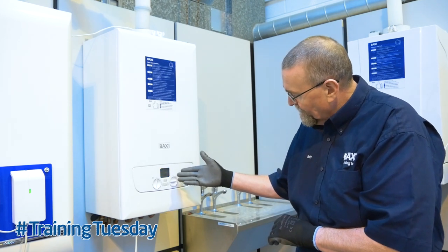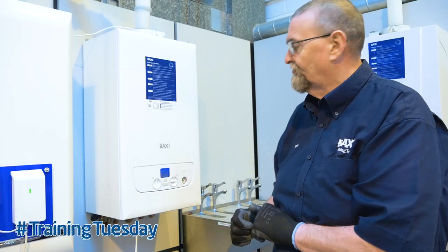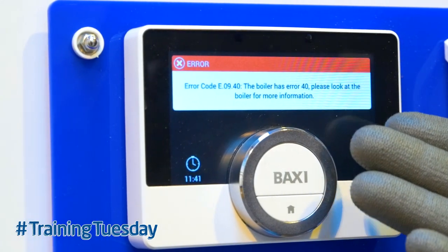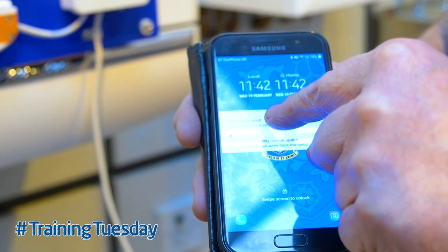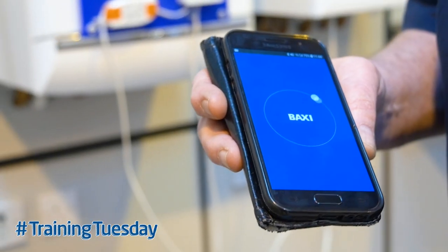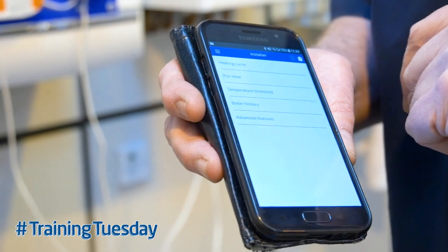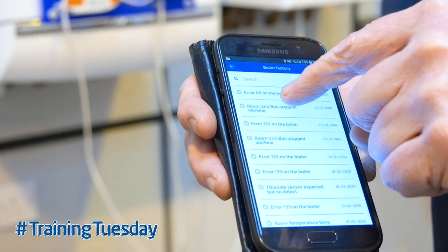As you can see, the boiler's flashing up an error code — we've got an E40 error code. Because it's wired up OpenTherm, that information is now sent to the control, so wherever that boiler is located — whether it's in the loft, in a cellar, or in a cupboard — the control has been sent a signal telling us we've got an error code. I've got the uSense app on my phone, and it's actually told me that an error has occurred — a new notification at 11:42. By accessing the app and going into the menu, we can see the E40 error occurred on the boiler.